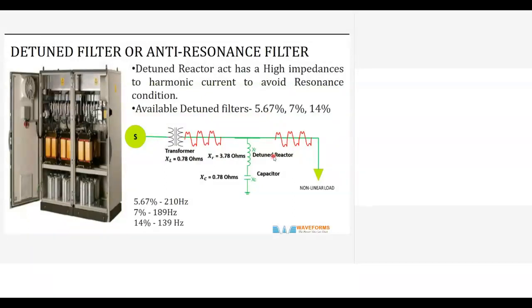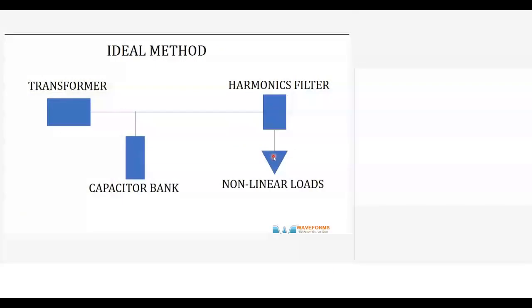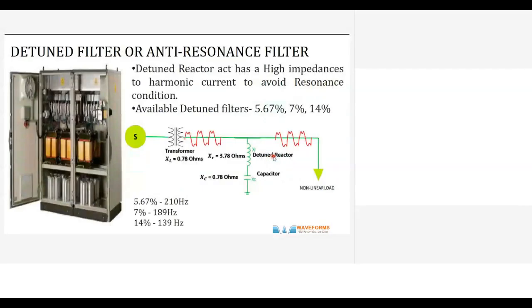But what does this percentage indicate? The percentage is the impedance of the inductor. Reactors are basically inductors. So when you have, say, 14%, the winding is more, so the magnetic flux induced will be more. So it is tuned to 139 hertz. When the detuned reactor and the capacitor interact, they generate a different frequency, 139 hertz, away from the 150 hertz. So it does block the third harmonic. Similarly, if you have the fifth harmonic, the 189 hertz is away from the 250 hertz.